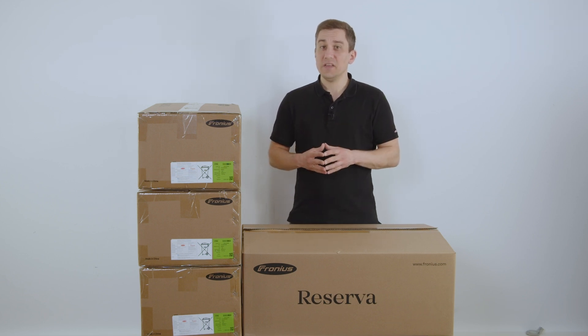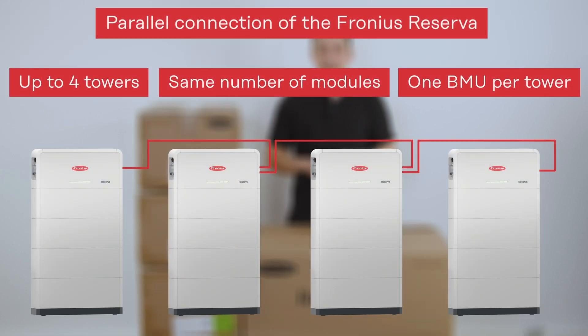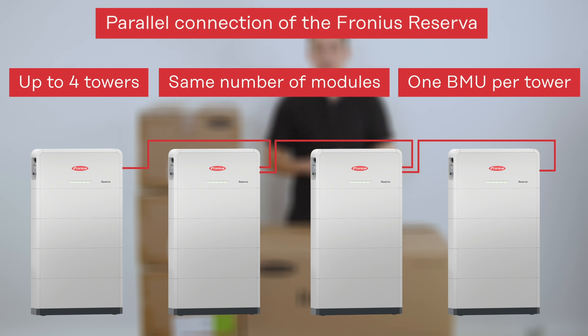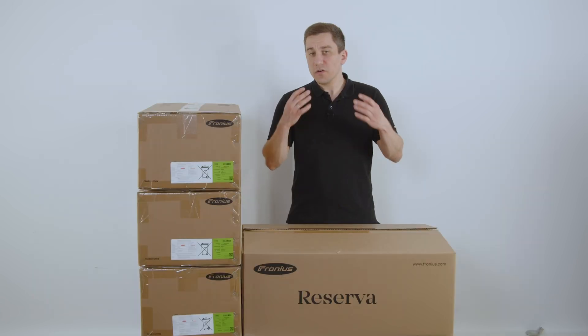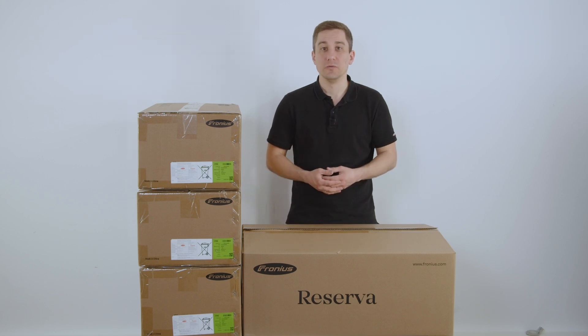Please note that when installing multiple battery towers you can place up to 4 towers in parallel. You always need to have the same number of modules within each tower and at least one battery management unit per tower. Let's start with the installation process and adding up the modules to each other.